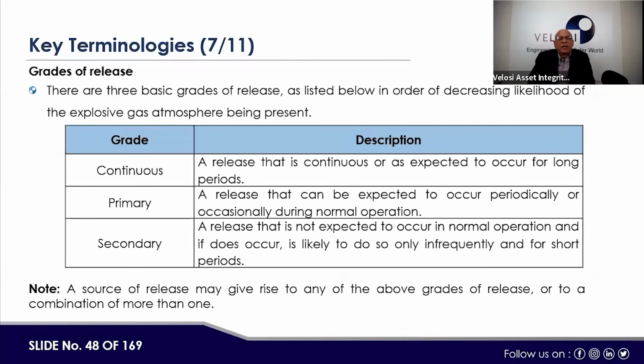Then grades of release, meaning how the hydrocarbon would be coming into the atmosphere. Continuous means a release that is continuous or expected to occur for a long period. Primary means a release that can be expected to occur periodically or occasionally during normal operation. Secondary is a release that is not expected to occur in normal operation, and if it does occur, is likely to do so only infrequently and for a short period. A source of release may give rise to any of the above grades of release or a combination of more than one together.